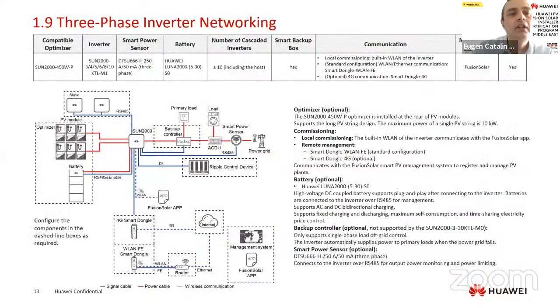Another scenario, with a three-phase inverter. Of course, using an M1 inverter, we can cascade a maximum of 10 inverters. The M1 is capable of installation in a cascading scenario with a maximum of 10 inverters. Again, if each inverter will have a battery, a maximum of 3 is recommended. We can also use an optional optimizer with a three-phase inverter. Of course, using a three-phase inverter, we will use only a three-phase smart power sensor. We can also have a backup box and a battery. And as I said, without a battery, 10 cascaded inverters.